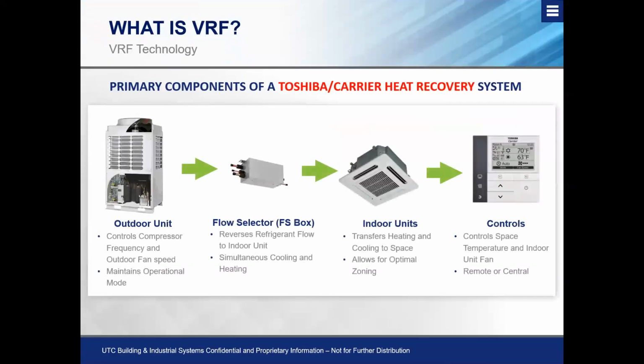Okay, so looking at the Toshiba carrier, same thing as we have with our carrier system. We have an outdoor unit, we have a flow selector box, or NDC, or branch box, whatever terminology you're comfortable with identifying that box as, an indoor unit in some form of control. Now the difference is if you look at this Toshiba carrier system, you'll see, commonly referred to as the three-pipe system, on this flow selector box, right here we have three pipes, which means we have hot gas, liquid, and suction going in and leaving the box depending on how that system is operating.